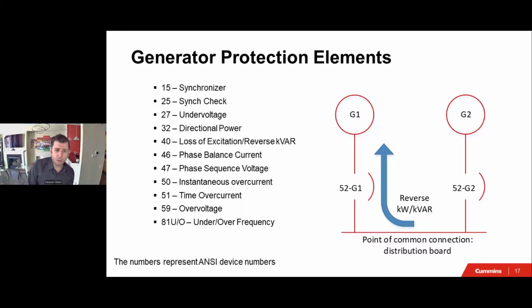And then there is also the protection. So this is load sharing. There's the protection. As a minimum, we need to protect against reverse kW, reverse reactive power. And then there's a synchronizer, sync checks, under voltage, over voltage, phase sequence imbalance. The numbers that you see in here are the ANSI designation numbers. You can look those up online and get a list of all these numbers. But as a minimum, we need to have some kind of protection on the generator sets.